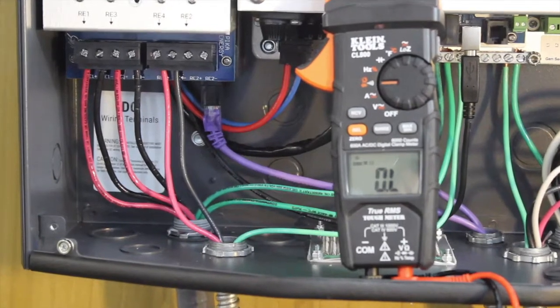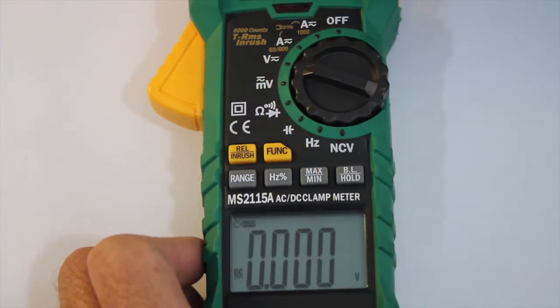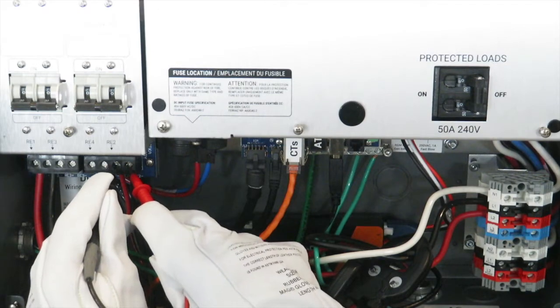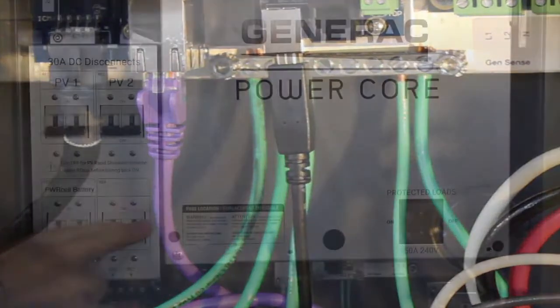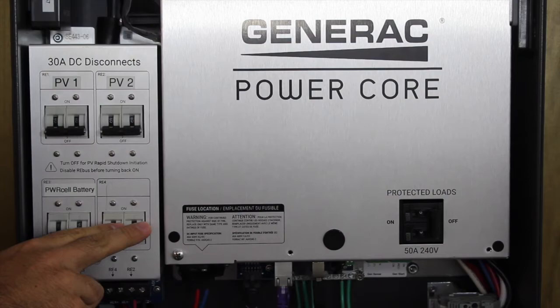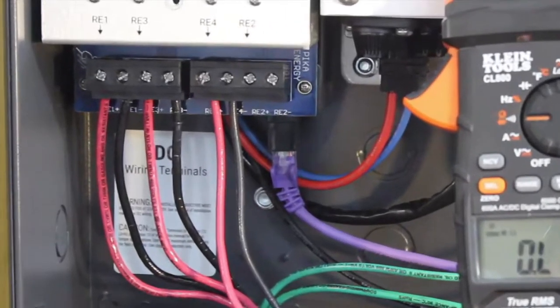Each REBUS device will connect to the inverter's bi-directional DC terminal with a positive and negative conductor. To prevent meter damage while measuring resistance, first perform a voltage test to ensure no voltage is present. REBUS devices are bonded to the ground terminal in the inverter. Ensure all PWRcell DC disconnects are off. All REBUS checks must be performed prior to energizing the system. Also ensure all DC connections are secure from inverter to REBUS devices.